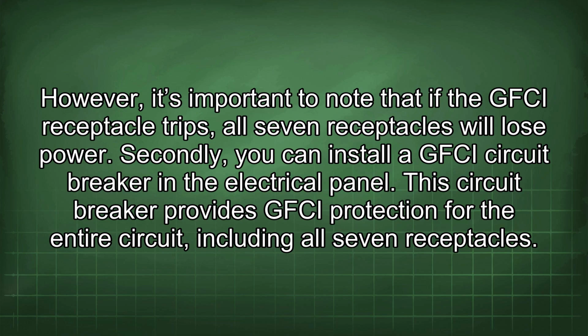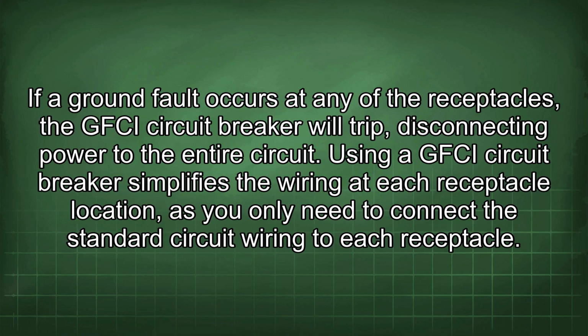Secondly, you can install a GFCI circuit breaker in the electrical panel. This circuit breaker provides GFCI protection for the entire circuit, including all 7 receptacles. If a ground fault occurs at any of the receptacles, the GFCI circuit breaker will trip, disconnecting power to the entire circuit. Using a GFCI circuit breaker simplifies the wiring at each receptacle location, as you only need to connect the standard circuit wiring to each receptacle.